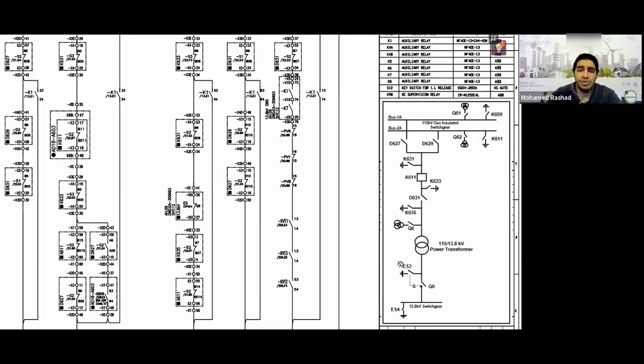I installed an isolator or disconnector switch for it. So now the issue of being withdrawable has become a replacement for what? It replaces the disconnector switch. That's why, if I want to close the ground, I must ensure that the breaker below is racked out, so that I can close my ground.